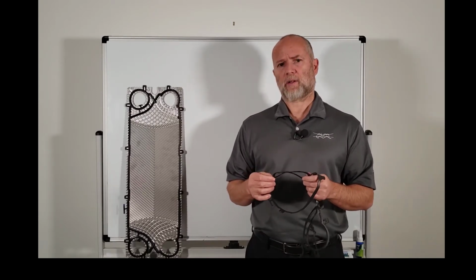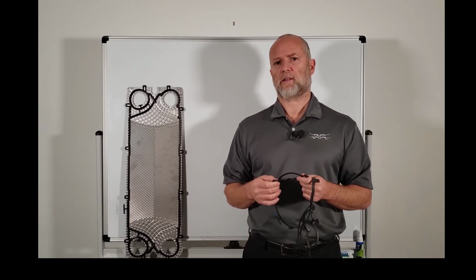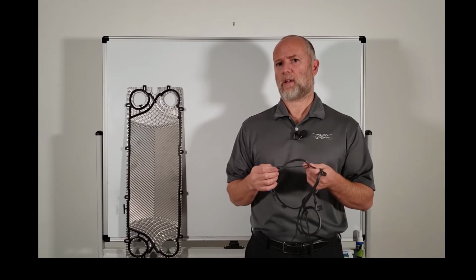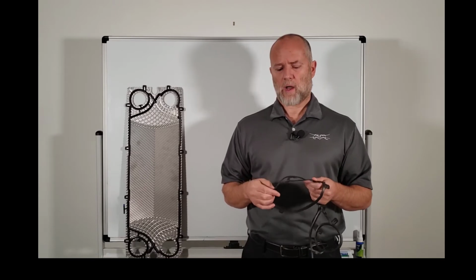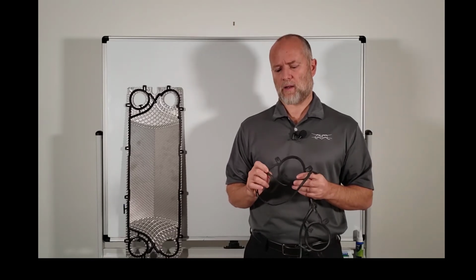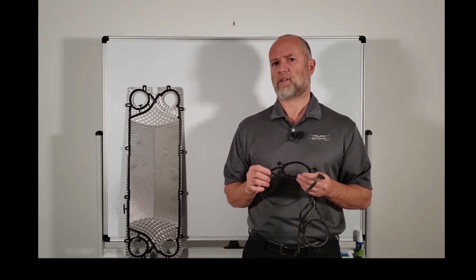In normal circumstances where there is no reason to open and close the heat exchanger, gaskets can last up to 15-20 years. Opening and closing the heat exchanger actually shortens the lifespan of the gaskets because the compression and expansion cycle affects the elastomer.